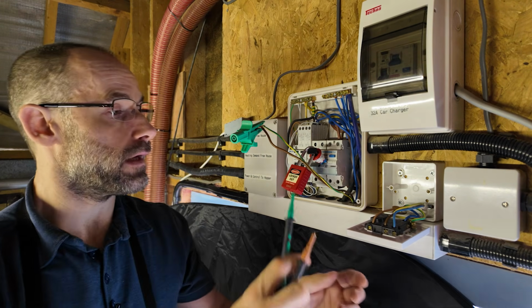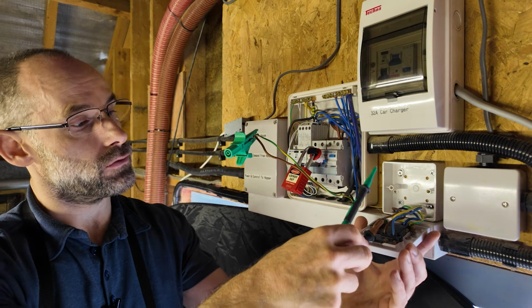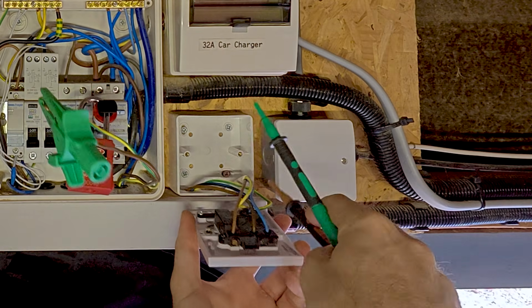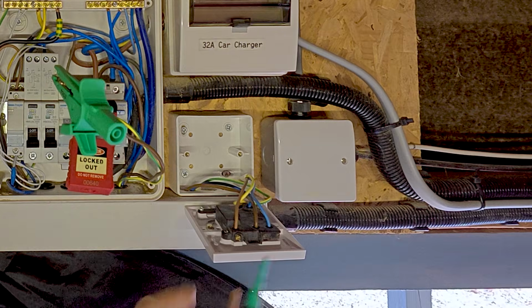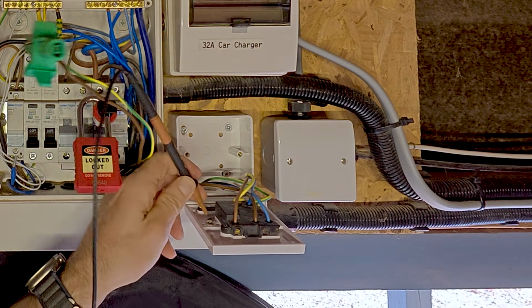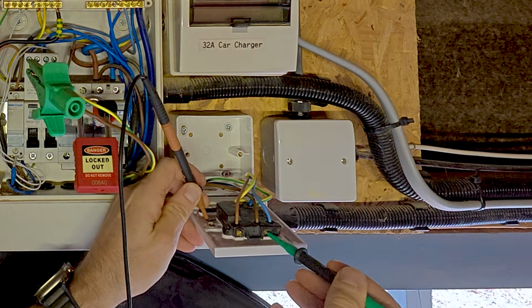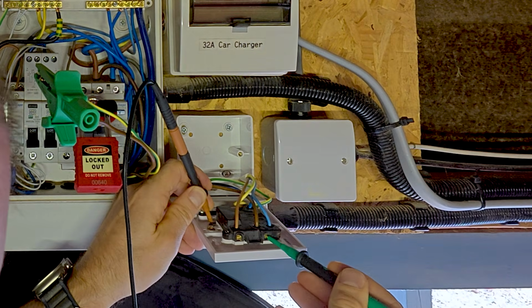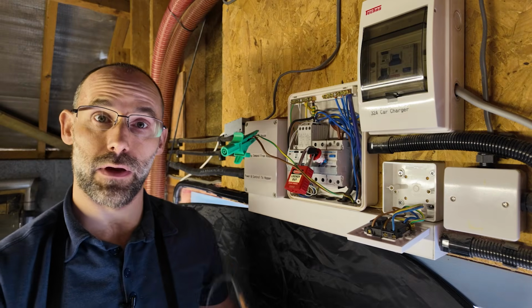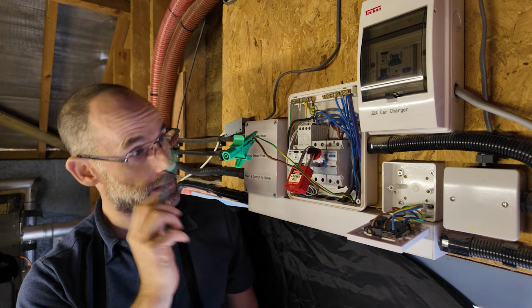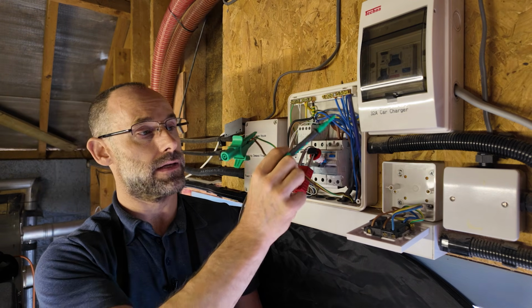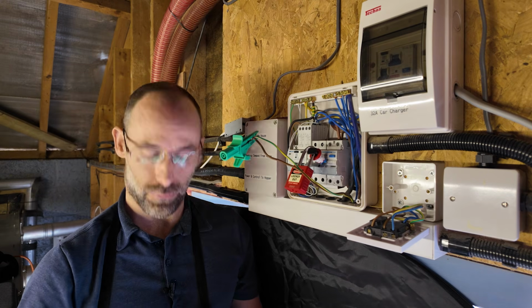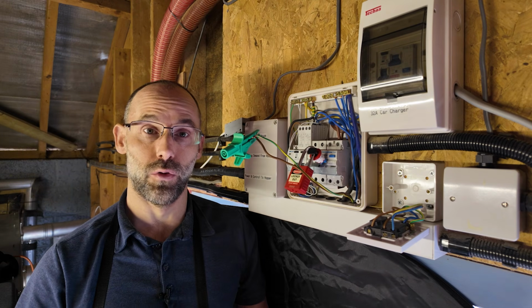All right, so what I need to do is find the incoming wires, really important. So this is this brown wire here, and in this particular case, the earth wire or the CPC. So I'm going to connect between these two, like so, and I'm going to see what resistance I get. Now, the beeping you hear means there is continuity. Those wires are connected. There is a complete loop between the line conductor and the earth or CPC, and the reading I got was 0.01 ohms.